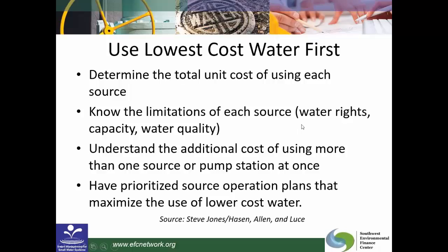And then you want to understand the additional cost of using more than one source or pump station at once. So if you are starting two pumps at the same time, you will have a higher peak demand than if you can start one pump and then wait the period that the energy utility charges for peak, and that could be 15 minutes, it could be 30 minutes, it could be an hour. But if you can understand what those additional costs are for running more than one source, more than one pump station, it will help you to reduce your costs.